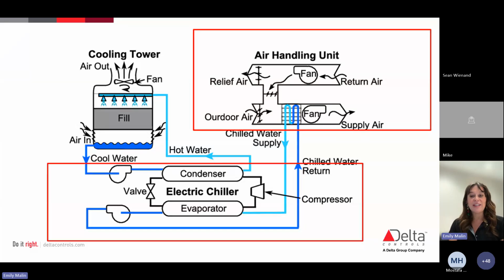Our second piece of this is going to be the chilled water itself, so going into chiller control. The sensors on the chiller are actually going to measure the temperature of the water that is coming back from the building. We're going to call that our chilled water return. And then it's also monitoring the temperature of the water that the chiller is sending out as well. So that's our water supply. Basically, if it senses that the water is coming back too warm, what you're going to see is that the chiller is going to increase its cooling output by adjusting its compressor.